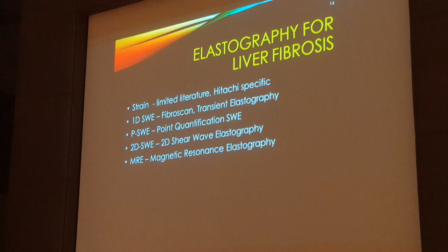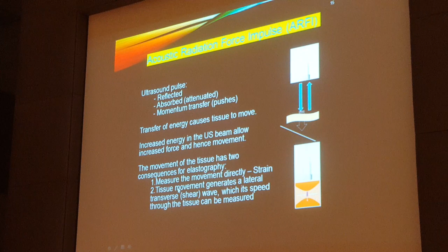So with the techniques we use, acoustic radiation force impulse, or ARFI, you all know that ultrasound pulses can be reflected, absorbed, or attenuated, or they can be momentum transfer pushes. And this ARFI pulse is generated so that it provides maximum momentum transfer, so it causes the tissue to move, and that has 2 consequences. We can look at the measurement directly, which is strain imaging, or we can look at the lateral or transverse shear waves. The speed of those shear waves is proportional to the stiffness of the tissue.